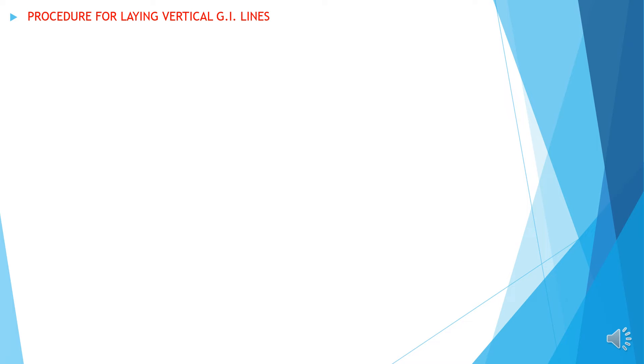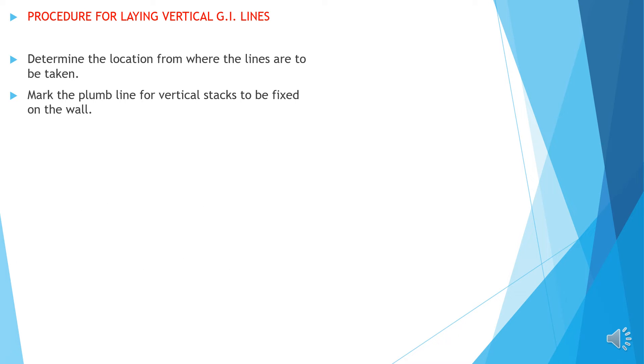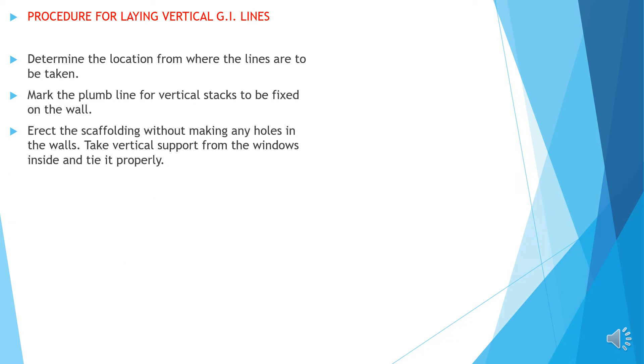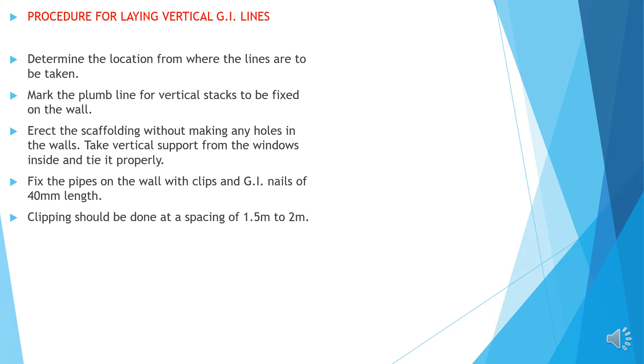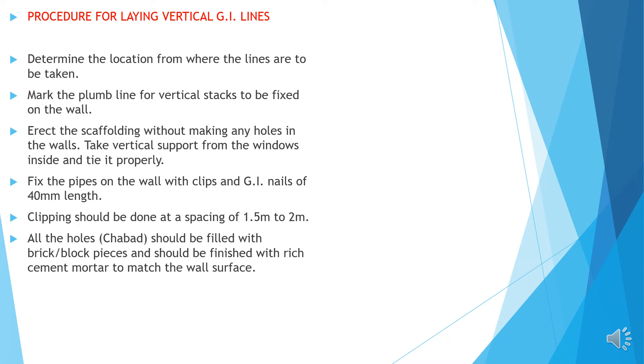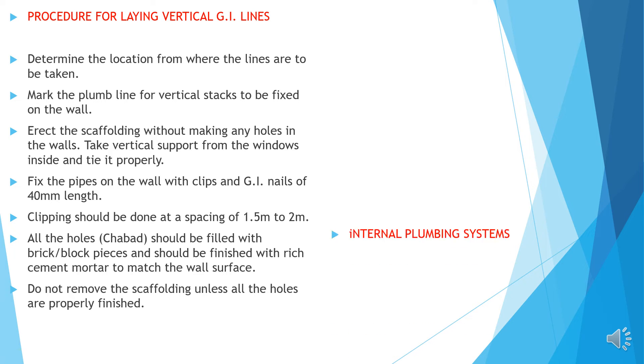Procedure for laying vertical GI lines. Determine the location from where the lines are to be taken. Mark the plumb line for vertical stacks to be fixed on the wall. Erect the scaffolding without making any holes in the walls. Take a vertical support from the windows inside and tie it properly. Fix the pipes on the wall with clips and GI nails of 40 mm length. Clipping should be done at a spacing of 1.5 to 2 meters. All the holes should be filled with brick block pieces and finished with rich cement mortar.